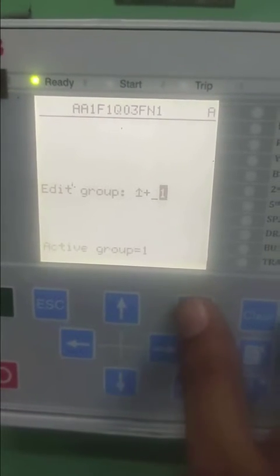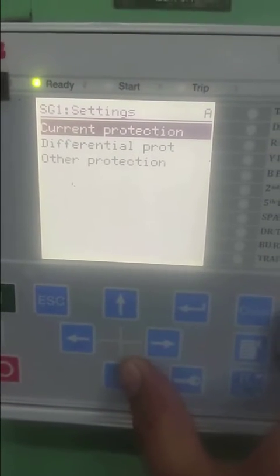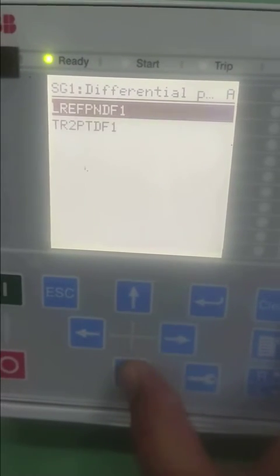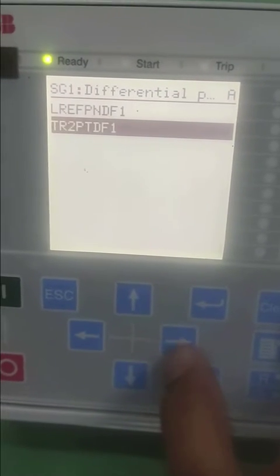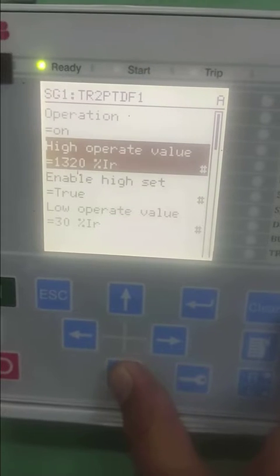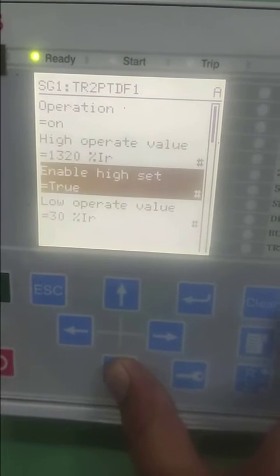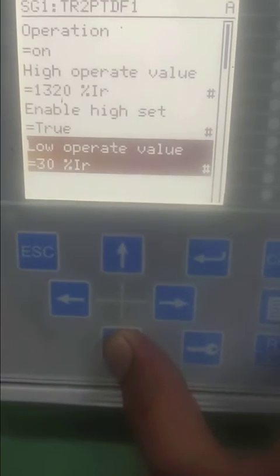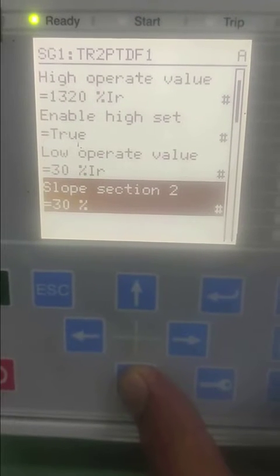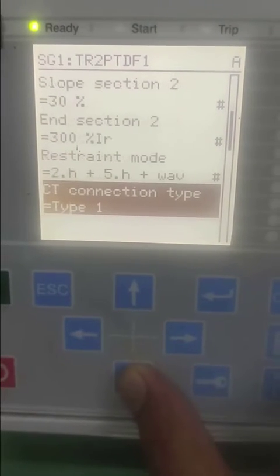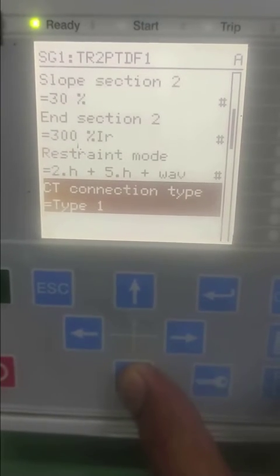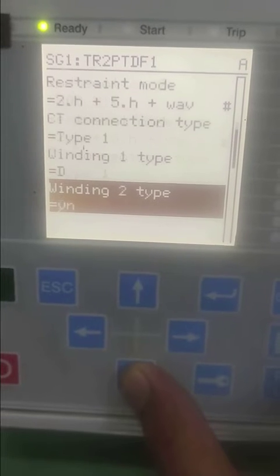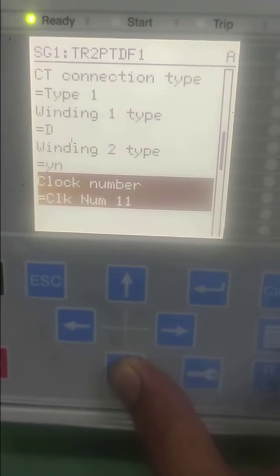Go to settings and select group one, then select differential protection TR2PTDF1. Here you can find out all the settings operation. This is used for 20 MVA transformer of 33 kV class, so you can find these settings.